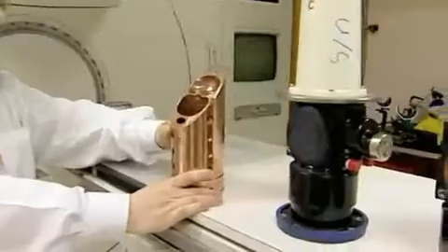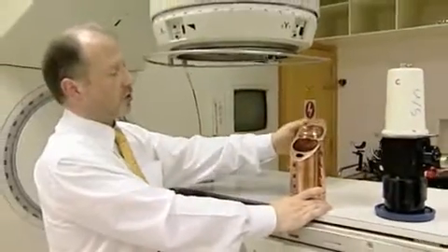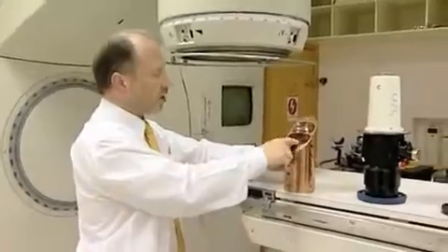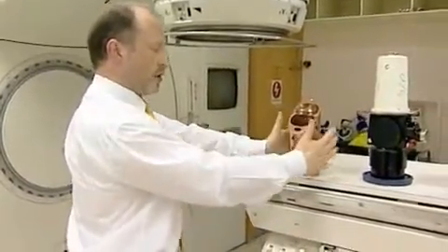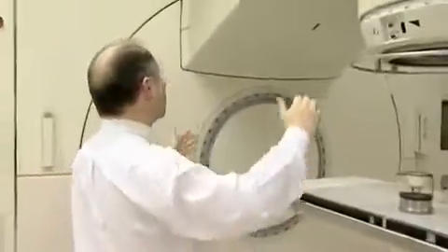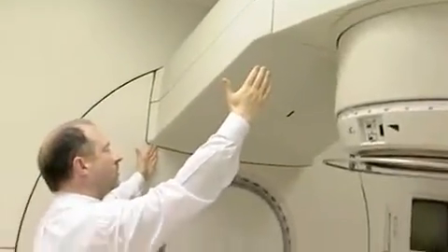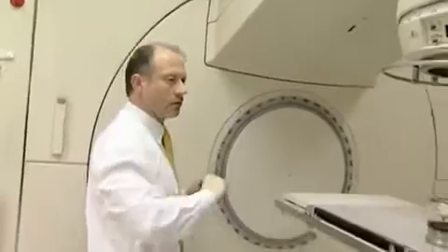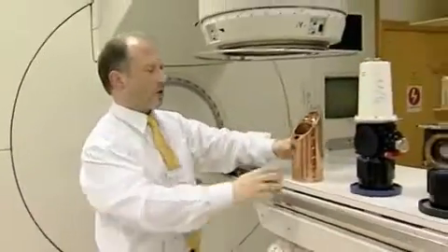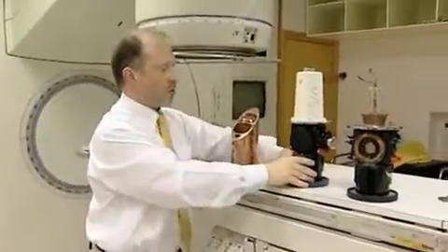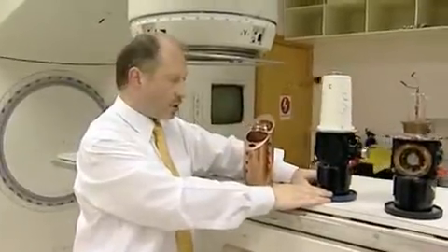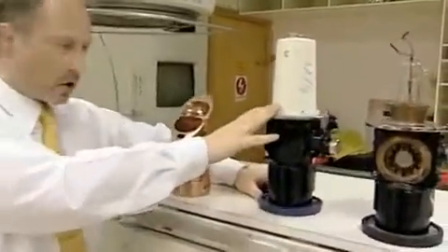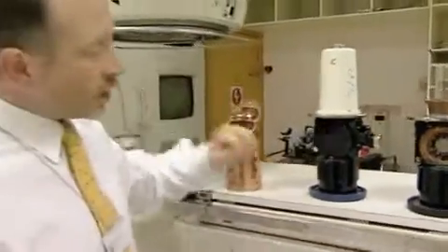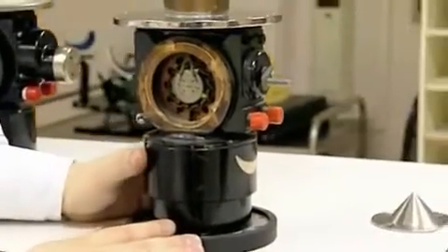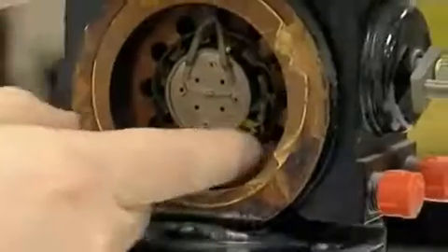Now the accelerating structure is basically a 1.5 to 2 meter copper tubing with accelerating cavities inside it. And this structure sits approximately here in the gantry of the unit. Now the electrons are accelerated down the structure by pulses of microwaves from a magnetron. And here we have an example of a magnetron. This is a cutaway example of the magnetron. And if we look inside it, we can see the accelerating cavities.